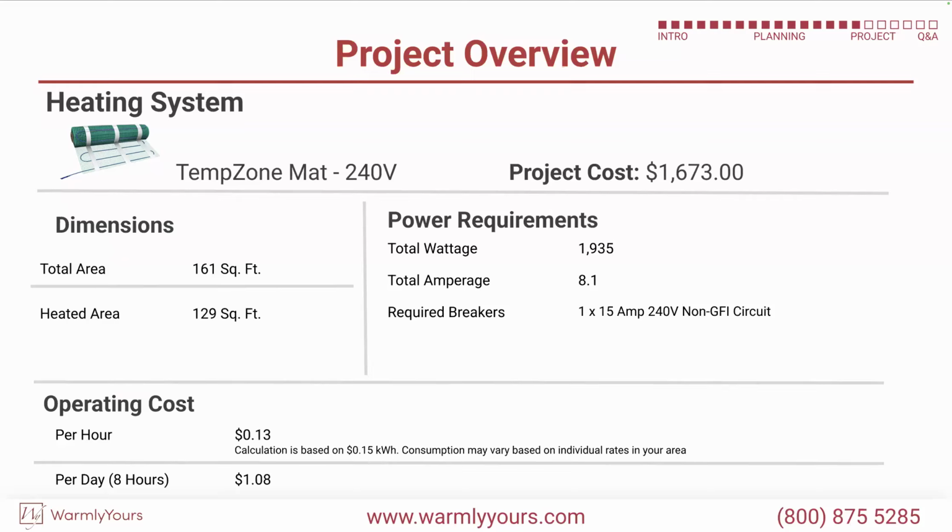That's it. And most of them we see are because electricians know that you have to have GFCI protection with floor heat, but some of them don't realize that the GFCI protection's in the thermostat. And now they've created a trouble with these two GFCIs fighting each other. So that's why it needs to be a non-GFCI circuit. And for those that aren't familiar with the GFCI, that stands for ground fault interrupter.